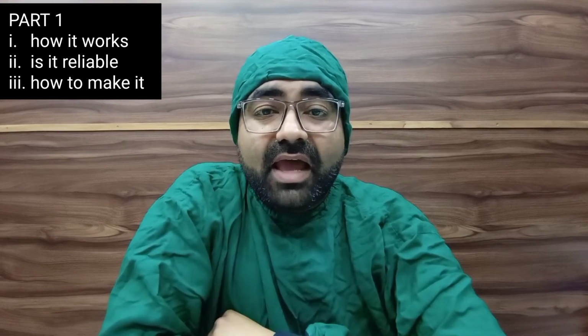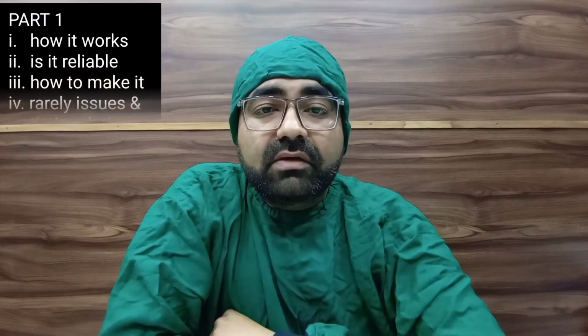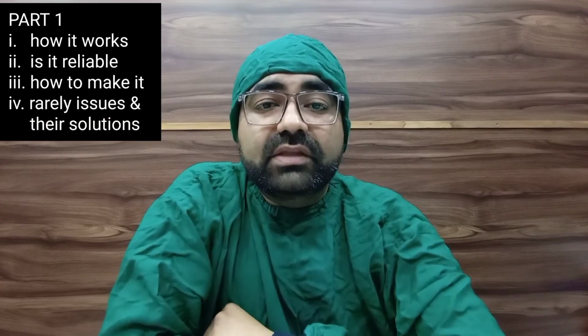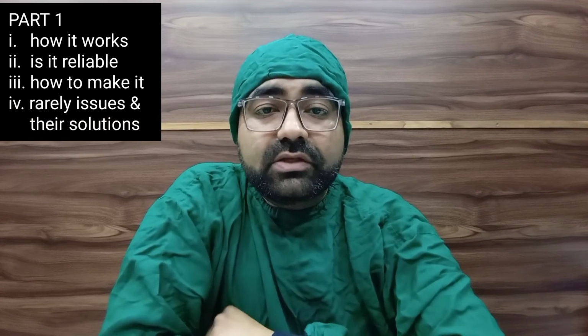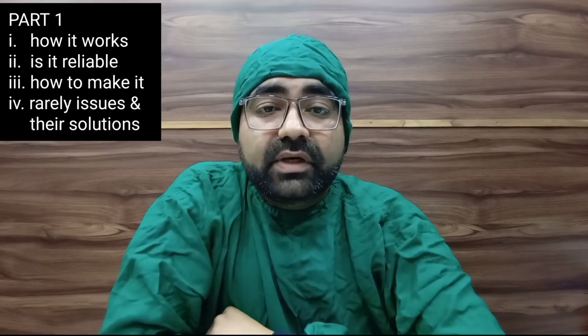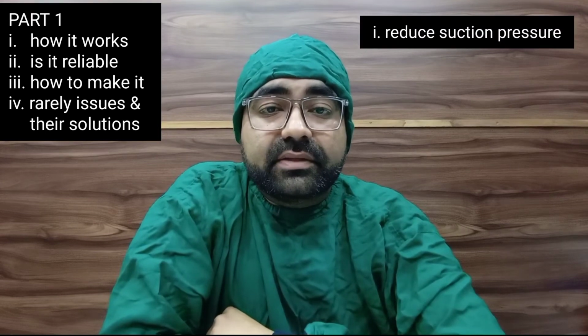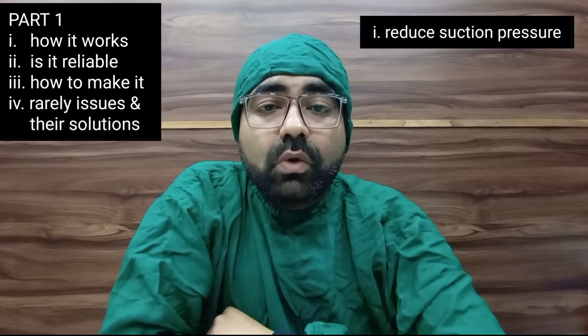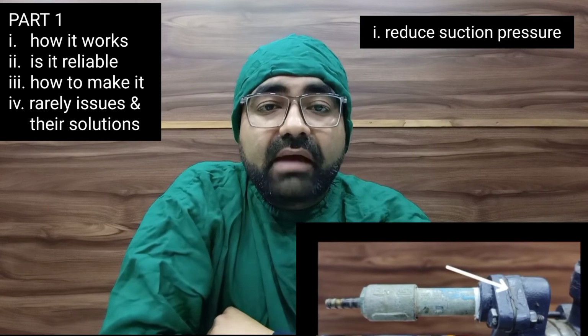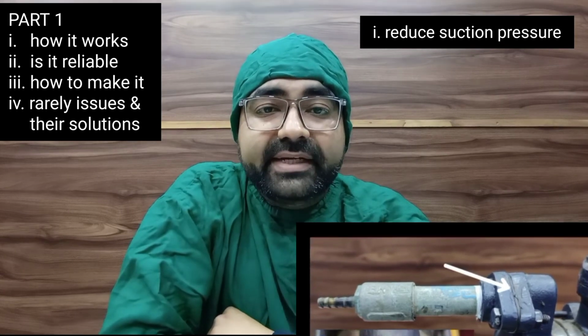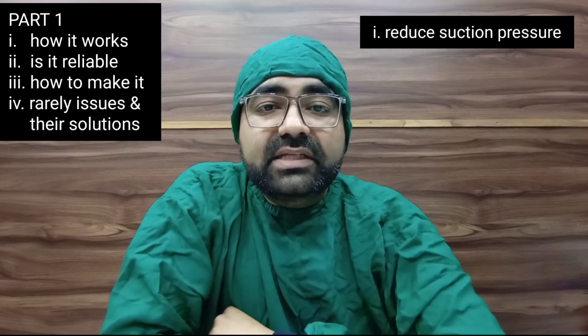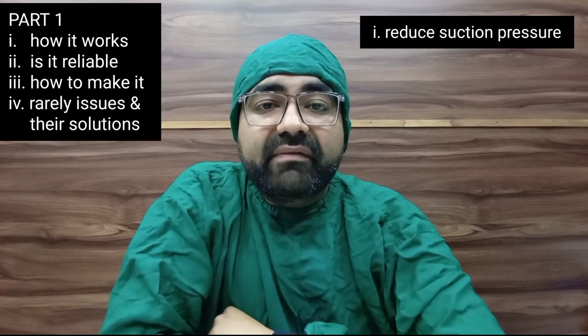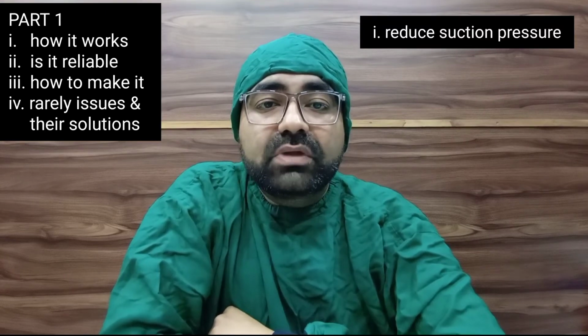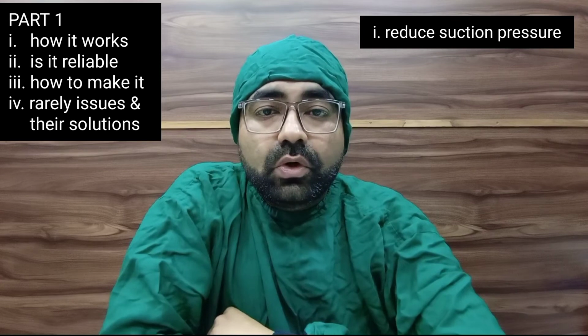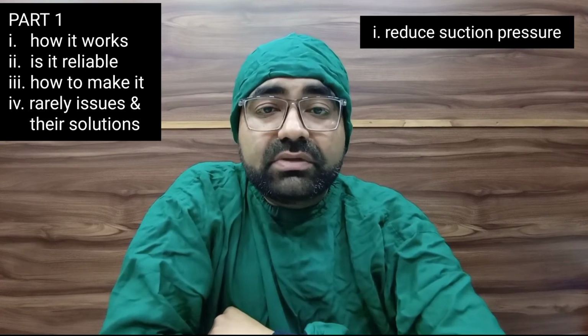Now, as always, I am more interested in complications, so I will mention a few rarely occurring issues with motorized suction and how you can solve them easily. First, reduced suction pressure: all good quality motor pumps have a small filter at the inlet end, used to prevent debris from entering the motor pump. When this filter gets clogged, the pressure of your suction reduces.